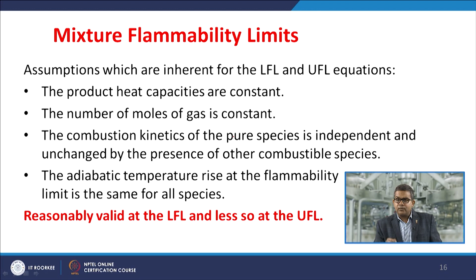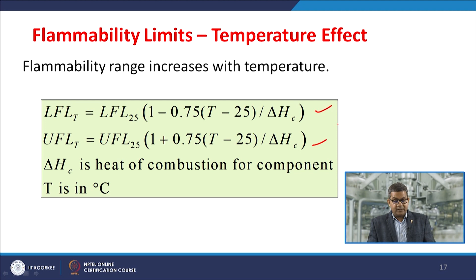In earlier slides we discussed that LFL and UFL are both impacted by temperature. These are the formulas through which you can assess the effect of temperature on LFL and UFL. The standard representation of LFL and UFL is at 25 degrees Celsius. So if you wish to determine the LFL and UFL at, say, 80 or 90 degrees Celsius, you can easily utilize these two formulas. LFL at a specified temperature T is equal to LFL25 into 1 minus 0.75 times (T minus 25) upon delta Hc. Delta Hc is the heat of combustion of the component, T is in degrees Celsius, and this is easily available in various handbooks. Similarly, UFL at a specified temperature is equal to UFL determined at 25 degrees Celsius into 1 plus 0.75 times (T minus 25) upon delta Hc.